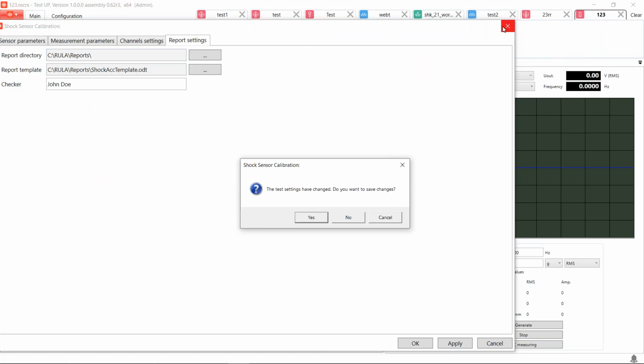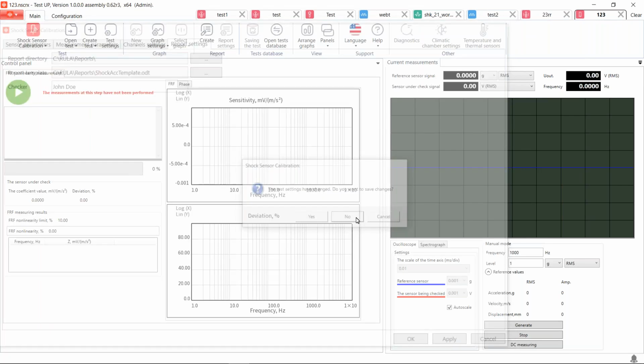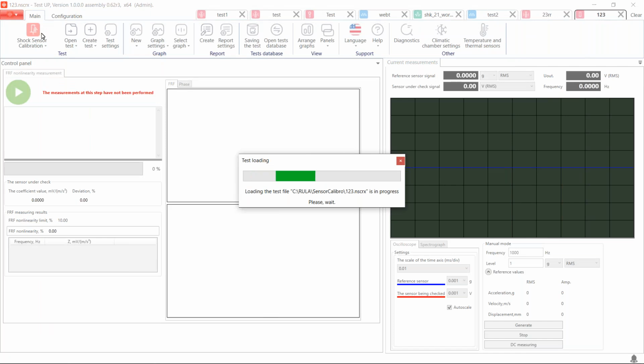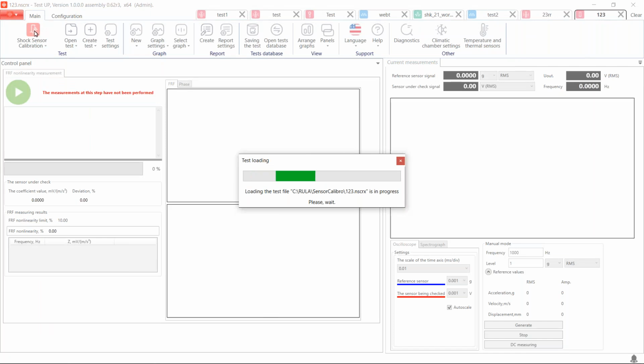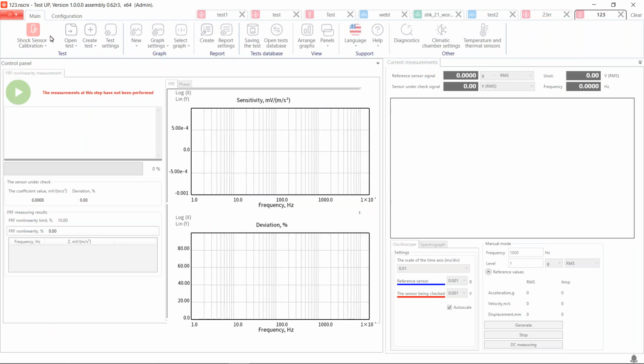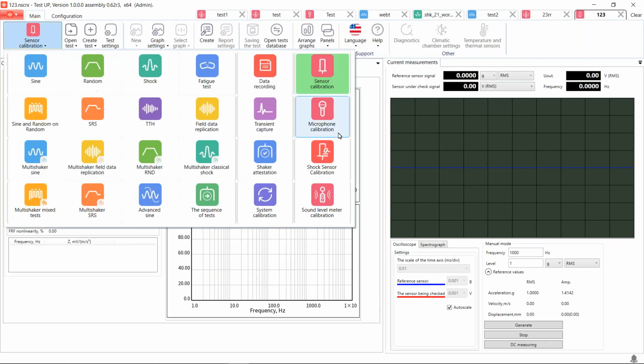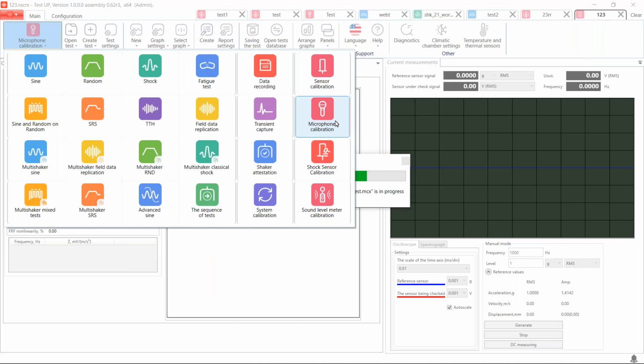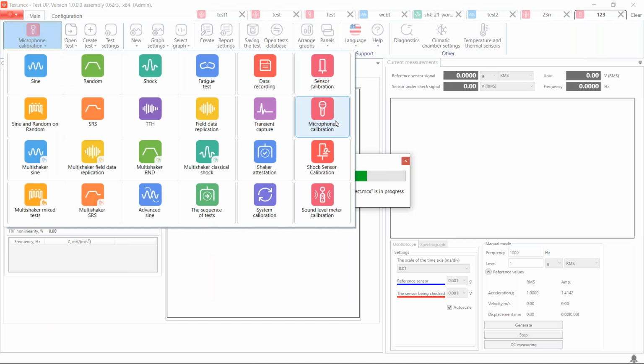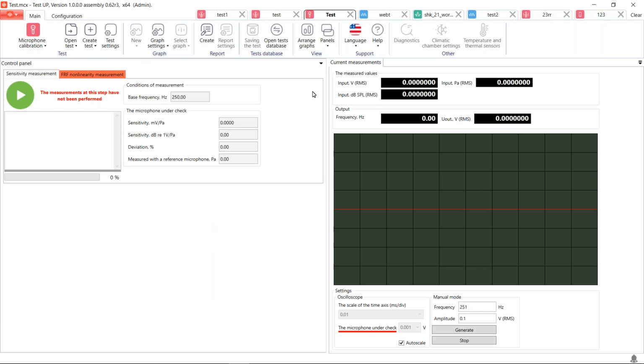Good. Now let's go to the procedure of calibration for microphones. Let's open it. Takes a little time. So while we're waiting, a few words about microphone calibration. The basic procedure of how to calibrate microphones is described in the standard IEC 61094. And this standard describes 2 methods of measurement, by sound pressure and by free field. Both of them are available in TestUp.